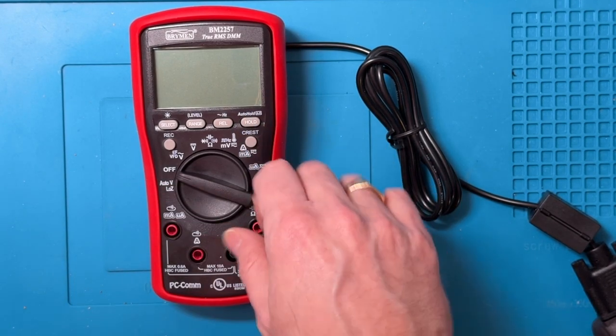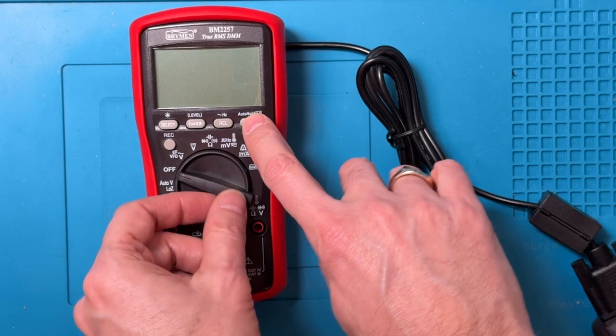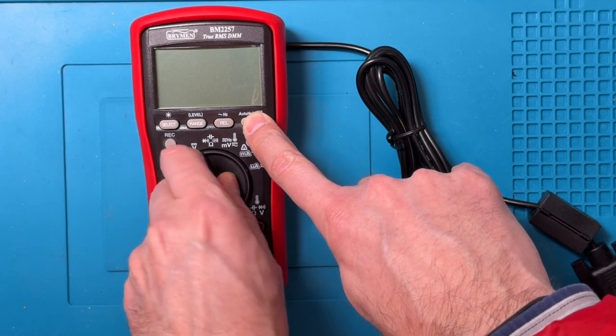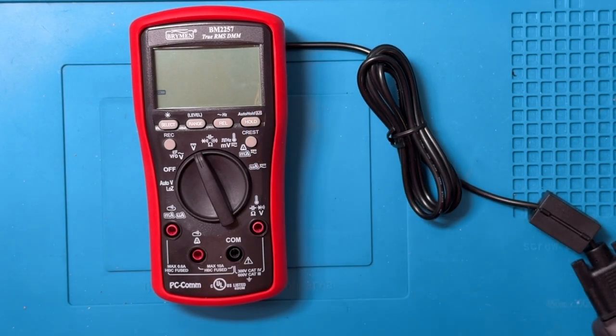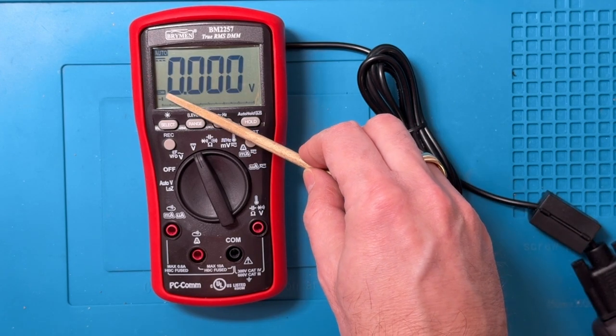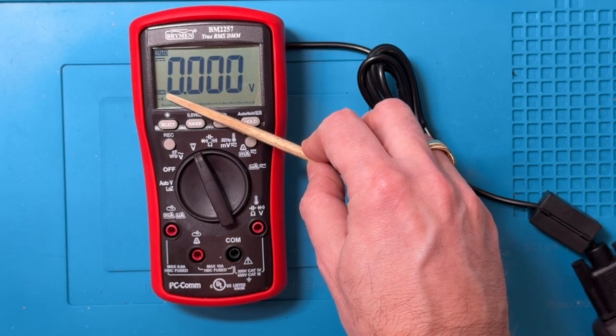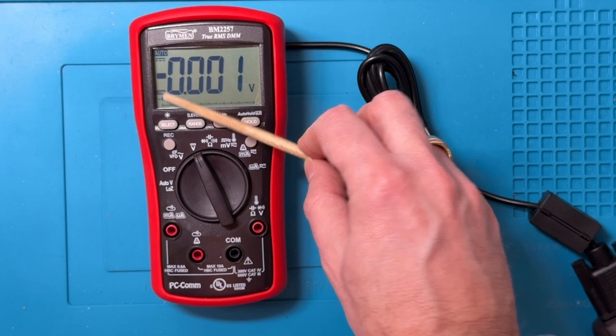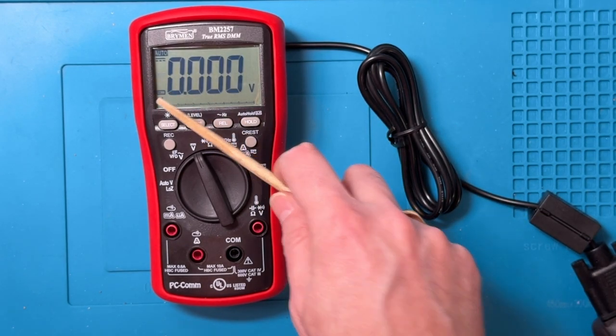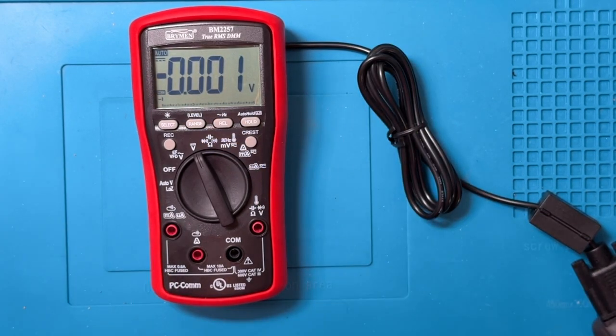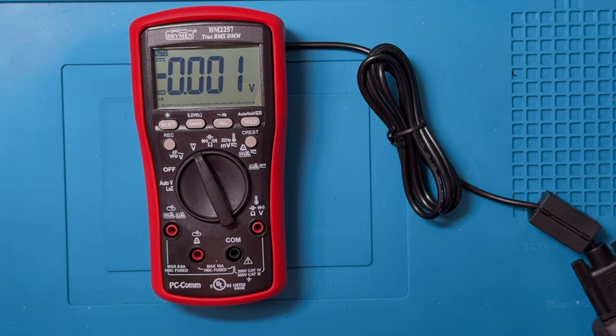You'd think they'd put something there to indicate that, but they don't. So we hold down the hold button and turn it on, and when we do that, there's a little COM indication that appears in the bottom left corner, which means the data logging or connectivity is activated on the meter side. Then of course you have to do all the rest of the rigmarole on the Windows side to get the connection going.